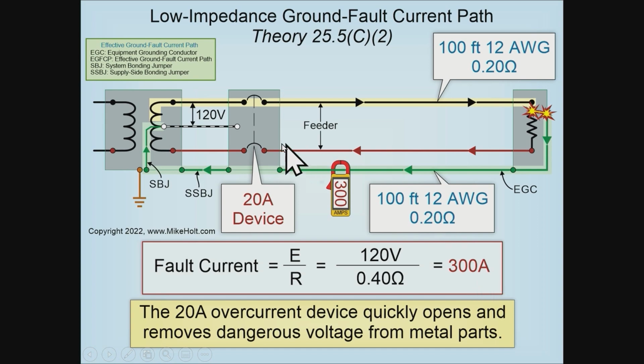Now this is 300 amps, and let's say this is a 20 amp breaker. And Tom, you said, hey, 99.99% of the time it'll probably trip instantaneous. Well, guess what happens if we do that? We take that circuit, we have a fault return path with low enough impedance to drive that fault current up so high that we can get it instantaneous. But that is all driven by the amount of available fault current that can even get there in the first place. So we didn't talk about short circuit currents as it goes down the line here. Assuming everything was perfect, and we ignore the arcing fault that takes place here and everything else like that, if we get instantaneous, but we don't know what it's going to be.